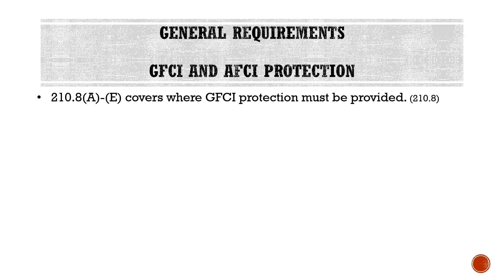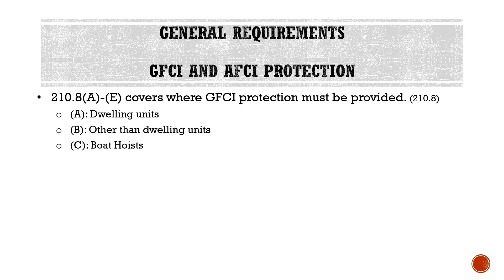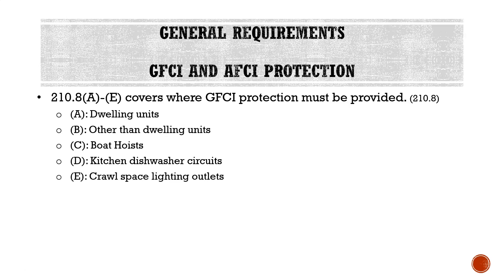Moving on to GFCI and AFCI protection. Section 210.8A through E covers where GFCI protection must be provided for different types of occupancies. Part A covers dwelling units, Part B is other than dwelling units, Part C covers boat hoists, Part D covers kitchen dishwasher circuits, and Part E covers crawlspace lighting outlets.